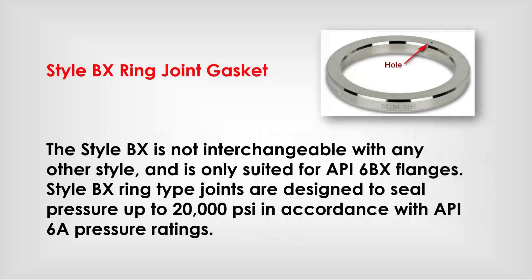Style BX is not interchangeable with any other style and is only suited for API 6BX flanges. Style BX ring-type joints are designed to seal pressure up to 20,000 psi in accordance with API 6A pressure ratings.